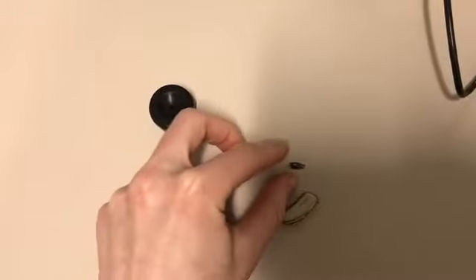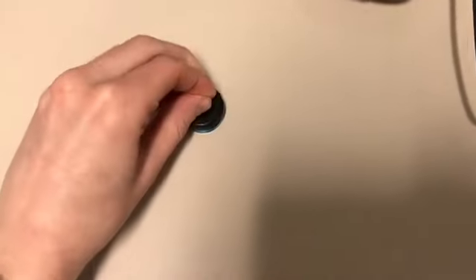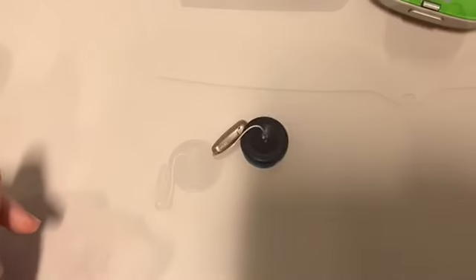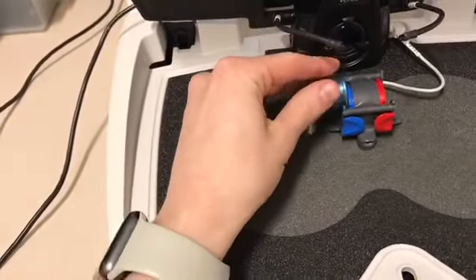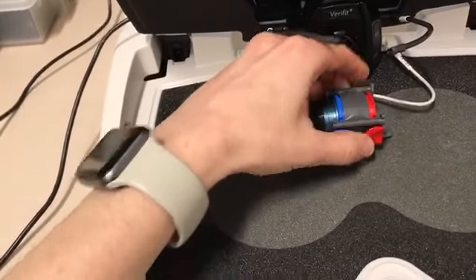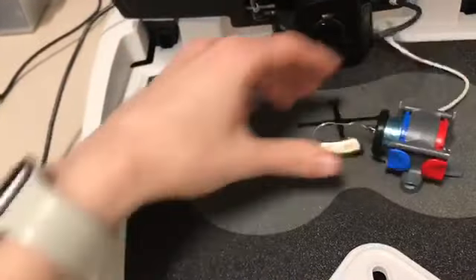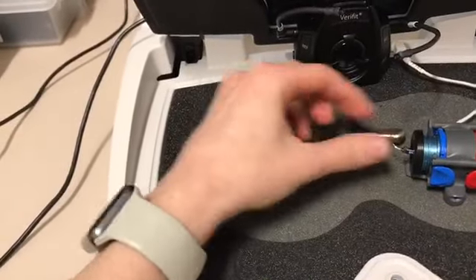So how do you ensure that noise reduction is working when you don't have an ear to run a real ear measure on? We can still run the same test in a test box with a 2cc coupler. Here we see Stephanie setting up the 2cc coupler inside the test box with the hearing aid attached. She maneuvers the hearing aid to have the hearing aid microphone face the speaker.